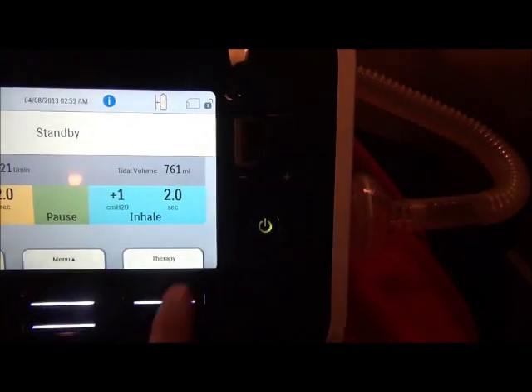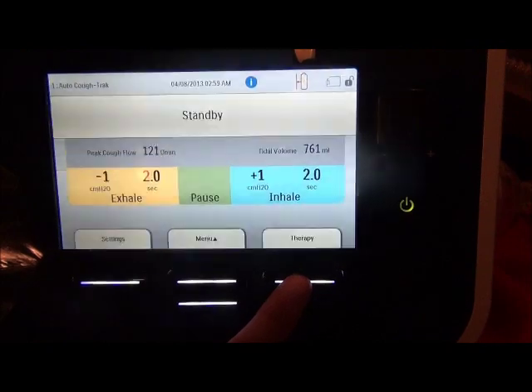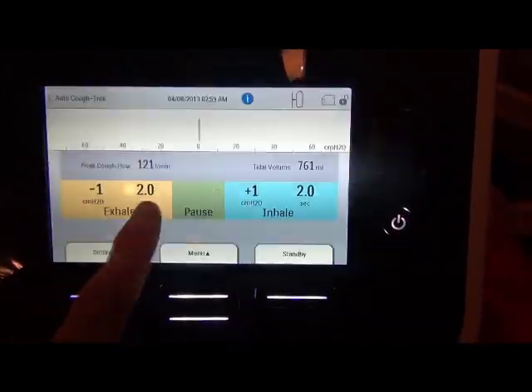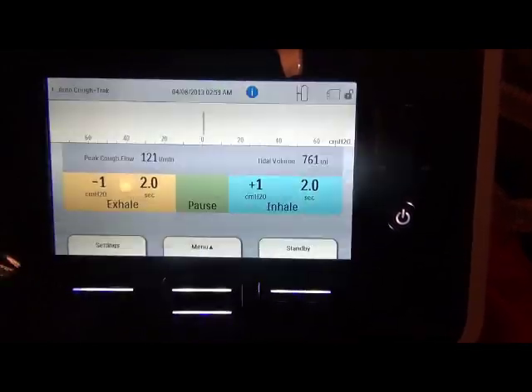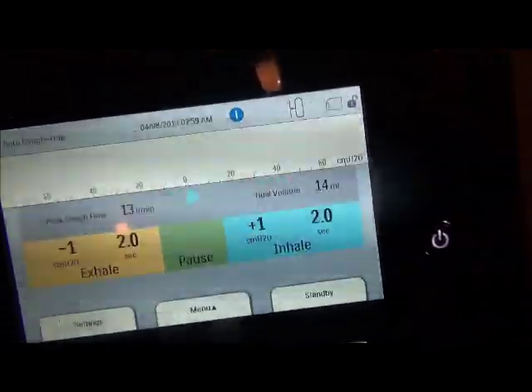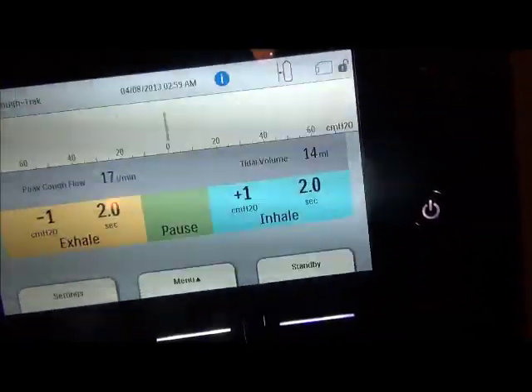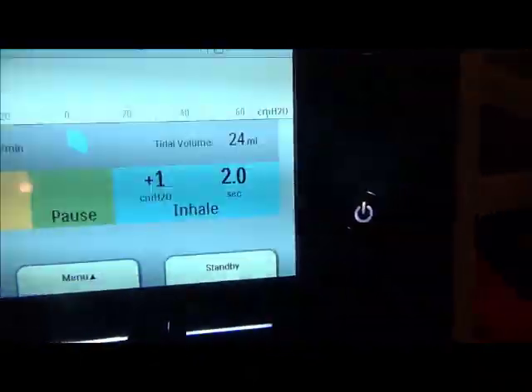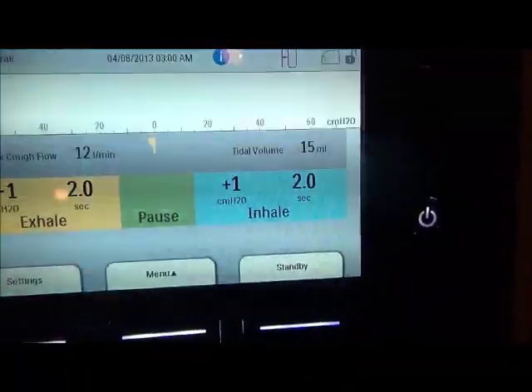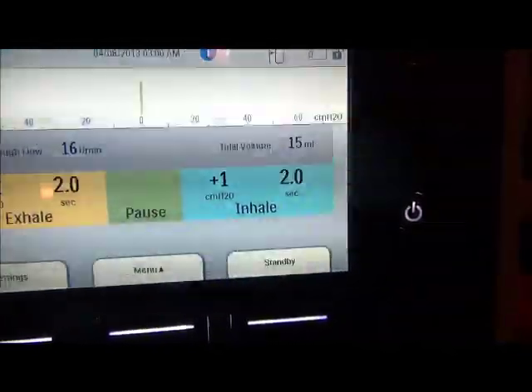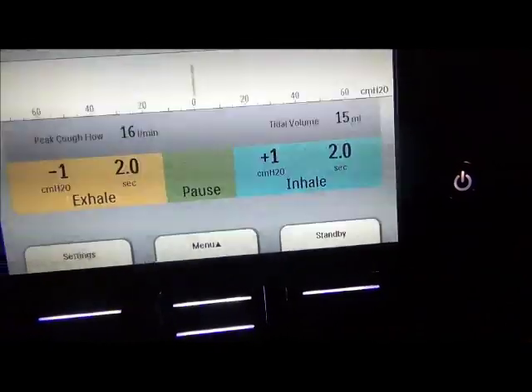Have this on auto, so I'm going to go ahead and turn on the therapy. Now we're at -1 +1. It seems like nothing's really happening right here. That's because the patient's really not giving a big breath. So I'm going to come up here to the calibration lung, and I'm going to push. So if you can look at that, I'm going to push this calibration lung, and I'm going to get some very low volumes and peak cough flow. Push really hard. So if this was an average patient, anything under 160 liters per minute would be a really bad situation for this patient.